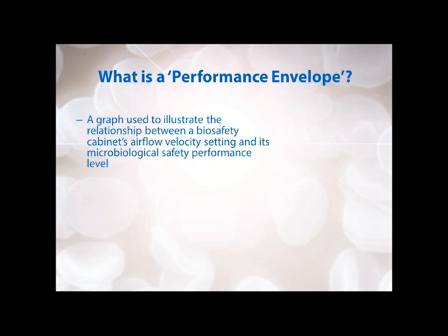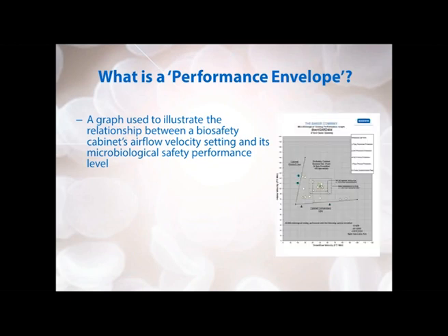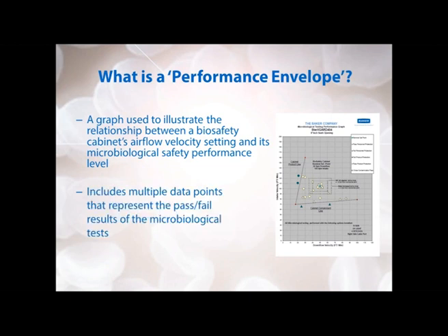So first, what is a performance envelope? The performance envelope is a graph that is used to illustrate the relationship between a biosafety cabinet's airflow velocity setting and its microbiological safety performance level. It includes multiple data points that represent the pass or fail result of the microbiological testing. There's also a series of lines that define the limits or boundaries based on these testing results.